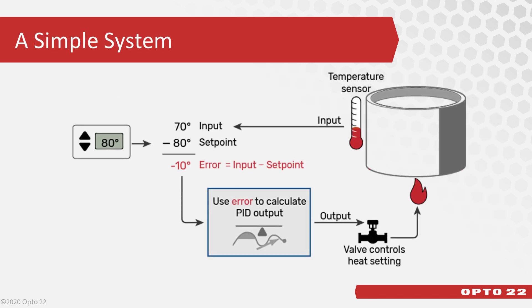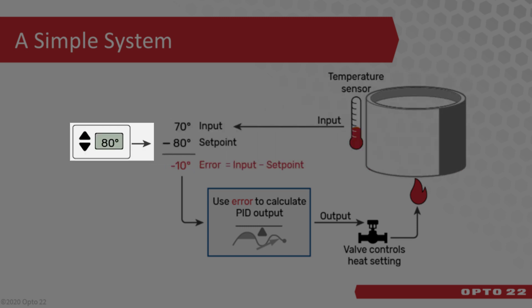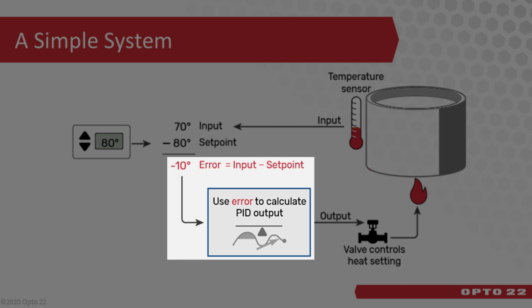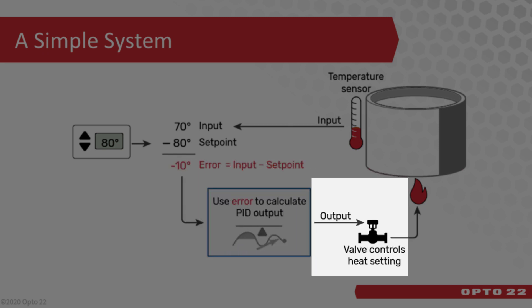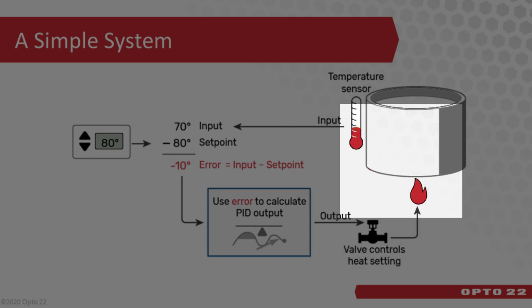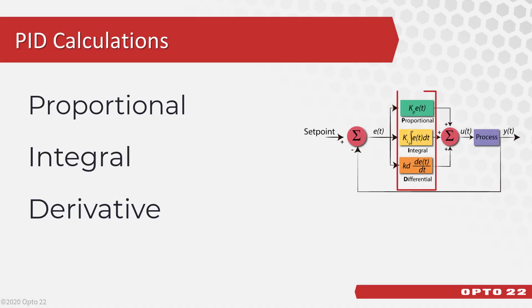In this simple tank heating system, the input or process variable is the temperature of the water in the tank, and the setpoint is set by a thermostat. The PID algorithm calculates the difference, or error, between the setpoint and input values. Using the error, the algorithm makes calculations to generate an output, which affects the process to get the input closer to the setpoint.